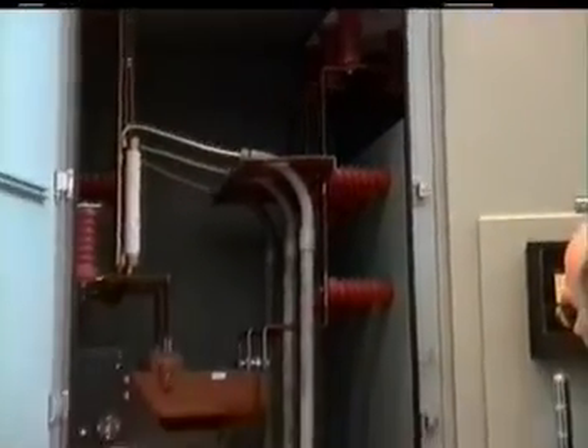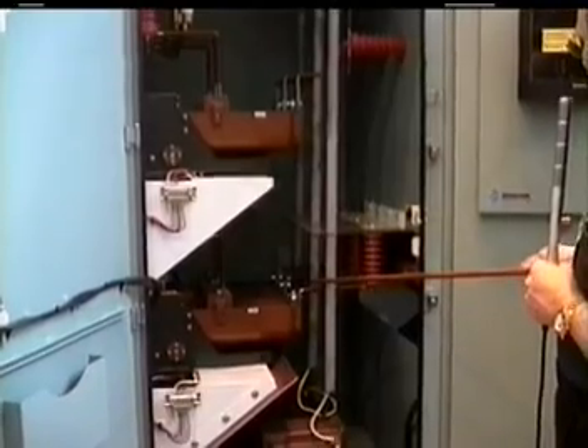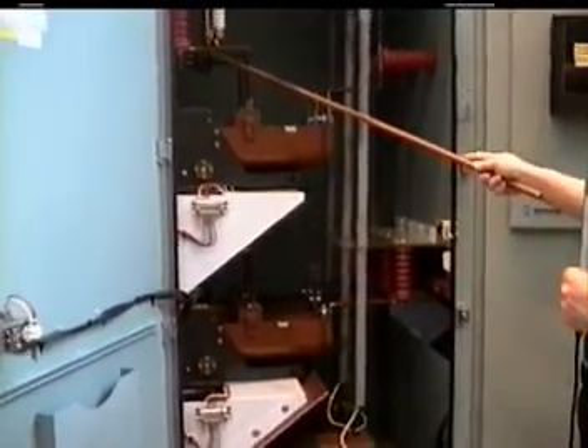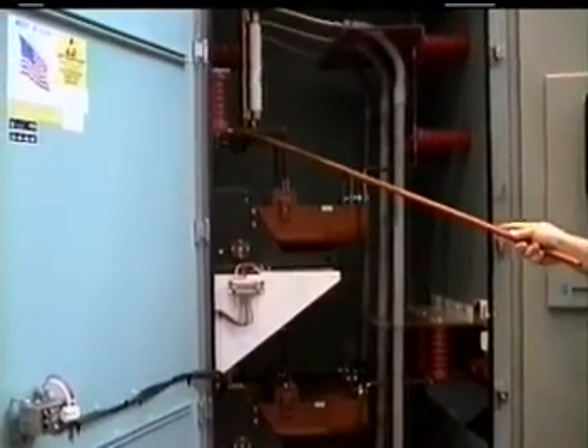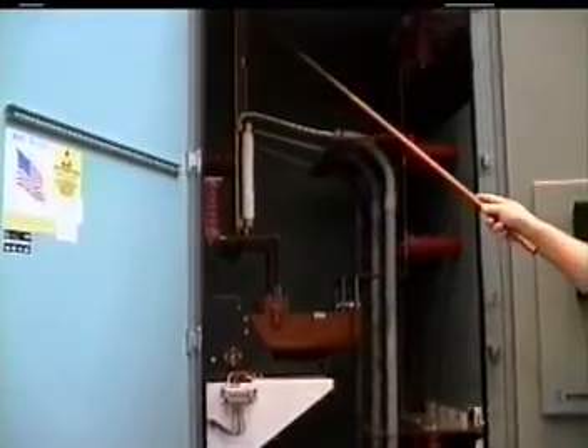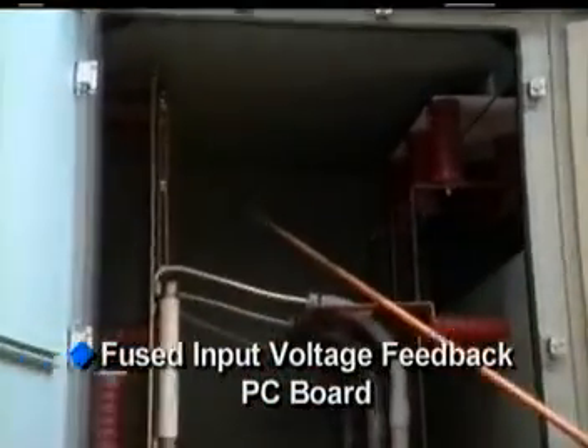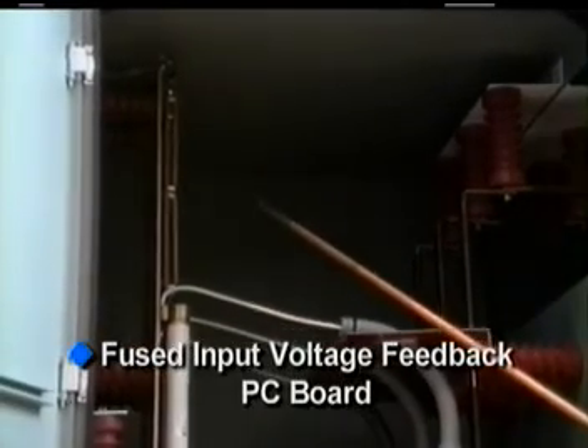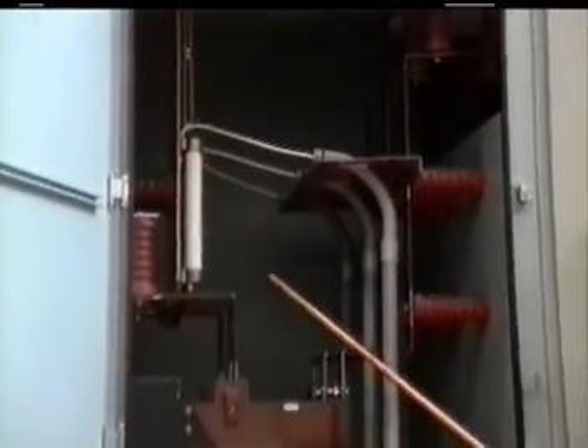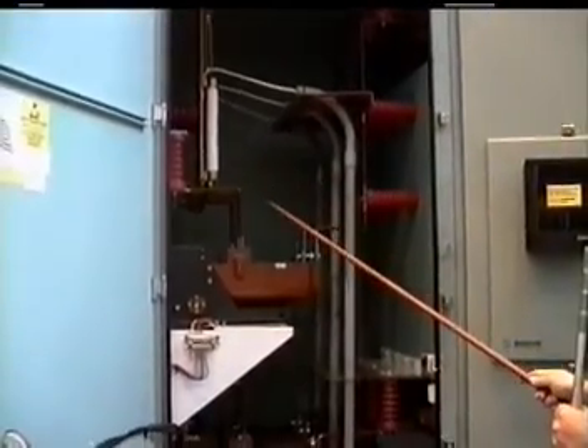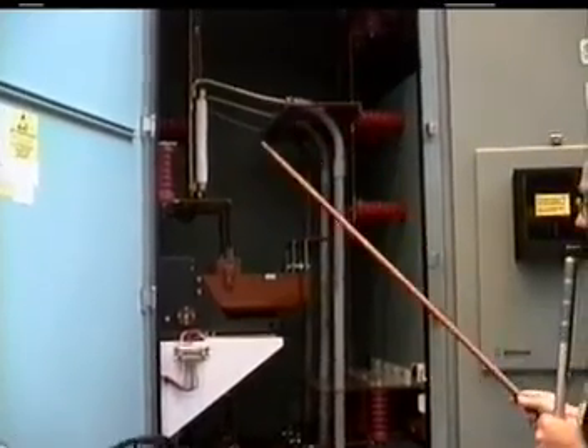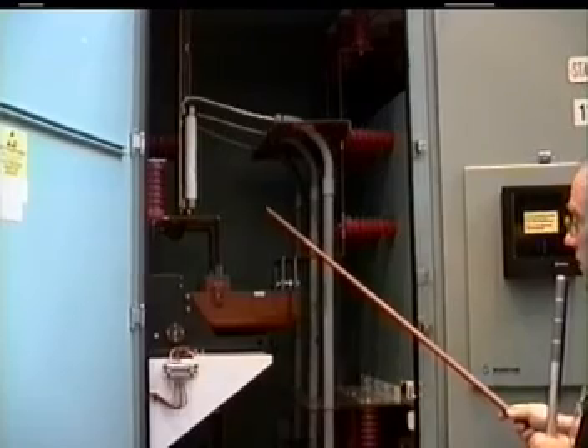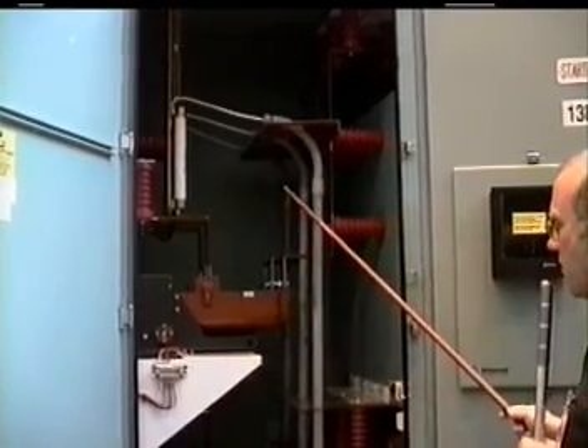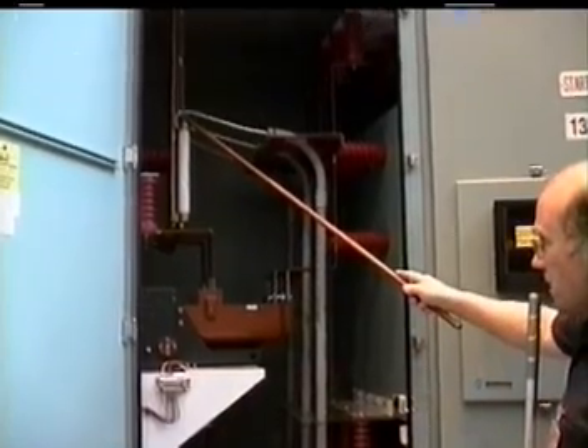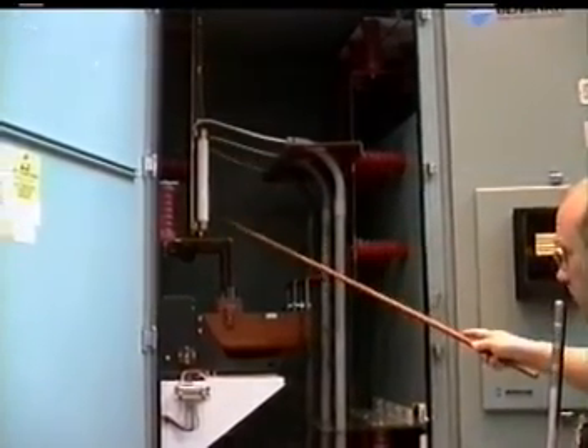This essentially becomes the power L connection to the input of the solid state stack. And we pick off of a section of the incoming bus right here and go through fuses to a resistor divider card to ground. The purpose of this resistor divider card is to provide a low voltage feedback signal that is used to determine the magnitude of the incoming 3-phase 13.8 kV voltage into the system, and also provides for phase sequence protection if desired, and also provides the phasing information as to when we can operate and fire SCRs.